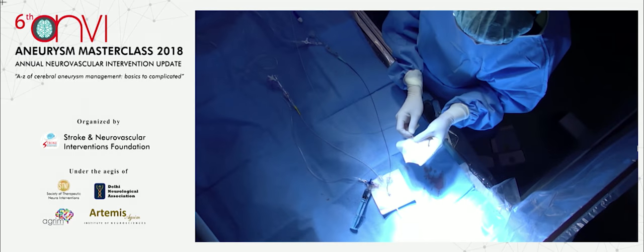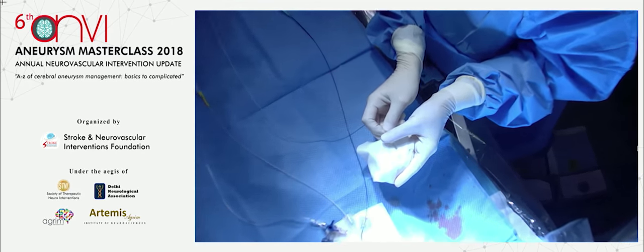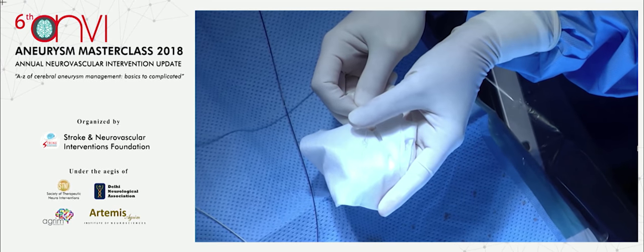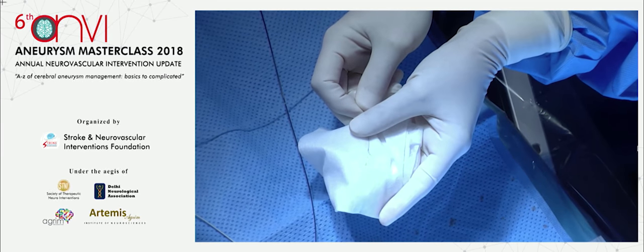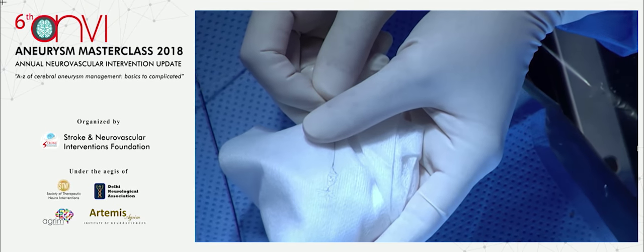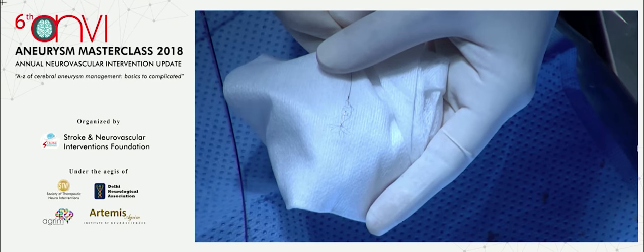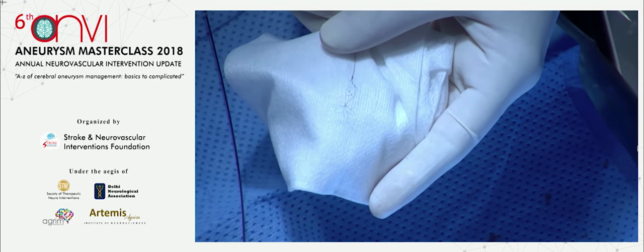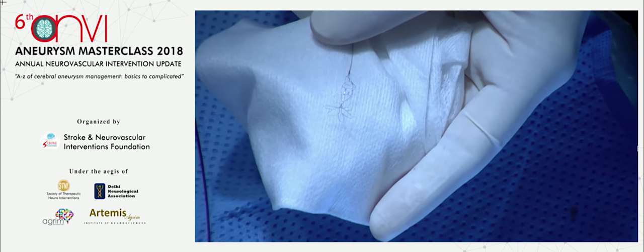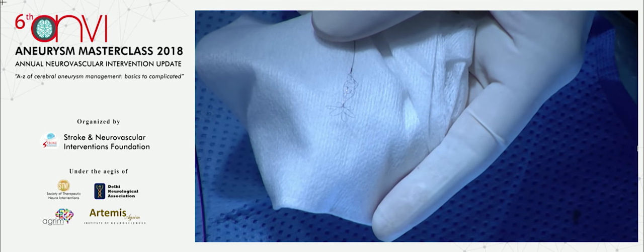The crown is essentially deployed inside the aneurysm. So, yeah, this works. That's beautiful. The crown is deployed inside the aneurysm. Then you pull the crown back. Exactly. Fantastic. So you pull down the crown towards the neck level, the entrance of the aneurysm. Then you fully deploy the device, and the device will be anchored in the parent artery by the shaft.